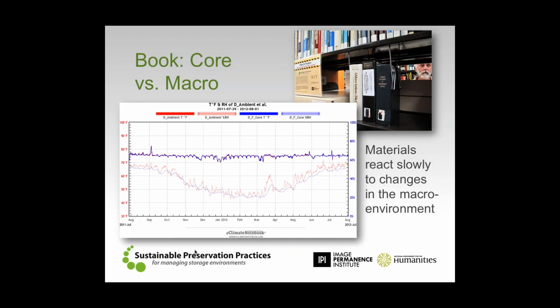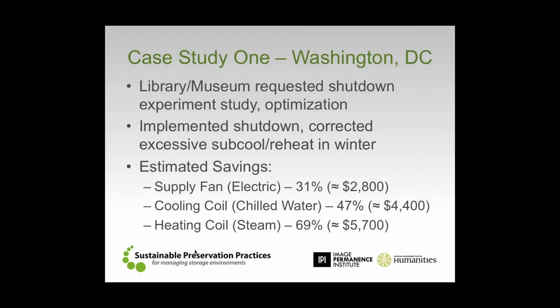And usually where we find acceptable shutdowns, the amount of fluctuation in terms of degrees, I usually look for no more than 2 to 3 degrees Fahrenheit fluctuation over the course of a shutdown period. Those small fluctuations over time are typically what a mechanical system is going to control to anyway. Ask any facility manager, it's awfully hard to get a system to run tighter than plus or minus 1 degree. But that 2 degrees worth of fluctuation is fairly standard for operation anyway. We're just doing it on purpose, in order to save energy, and realizing that there's very little preservation impact in terms of rates of decay as a result.